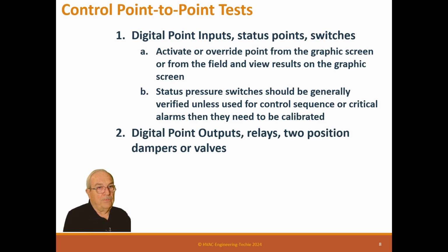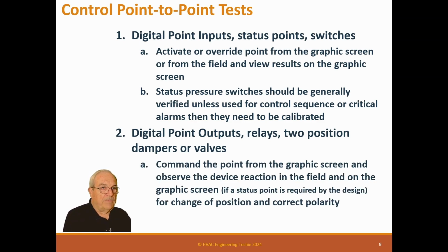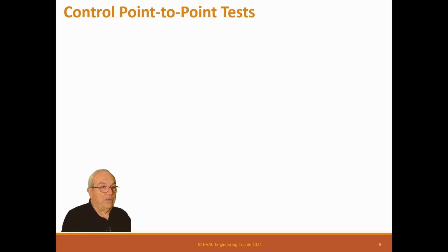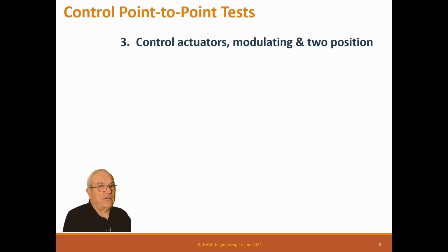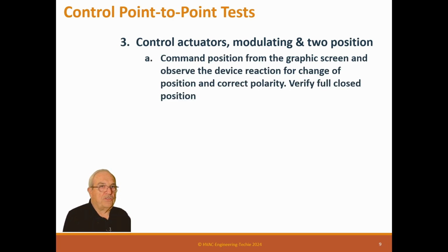Digital point outputs, relays, 2-position dampers or valves. Command the point from the graphic screen, observe the device reaction in the field and on the graphic screen. If a status point is required by the design, sometimes they're not, check for change in position and correct polarity. Control actuators modulating and 2-position: command the position from the graphic screen and observe the device reaction for change in position and correct polarity.